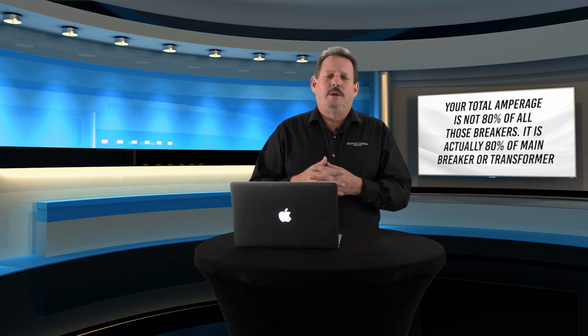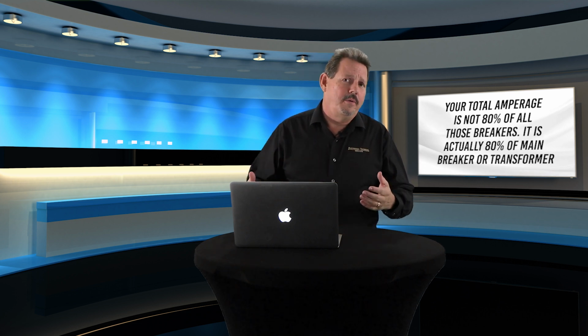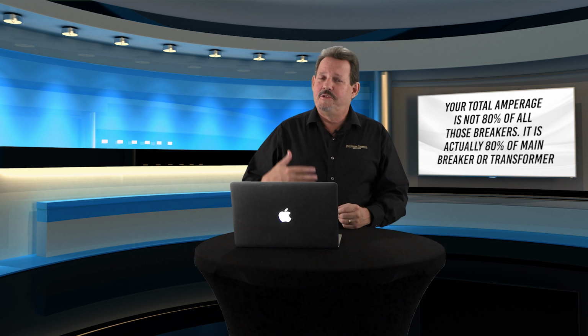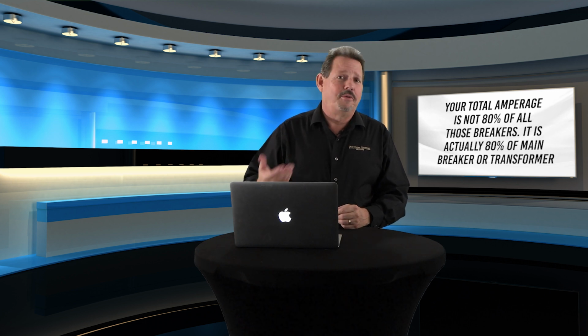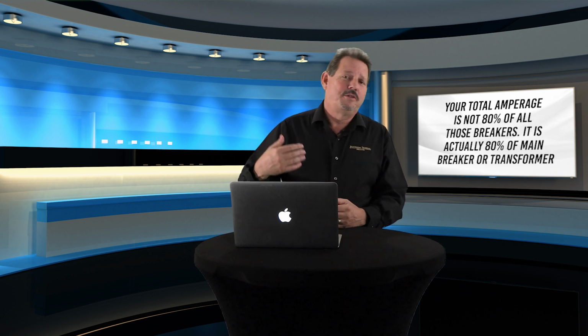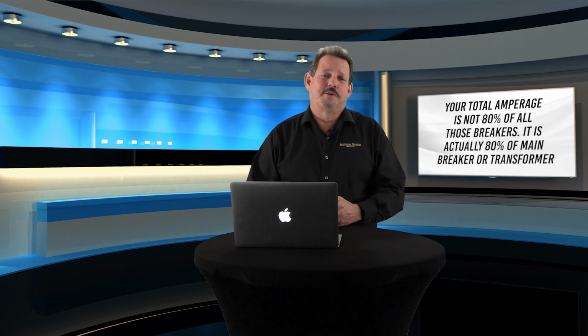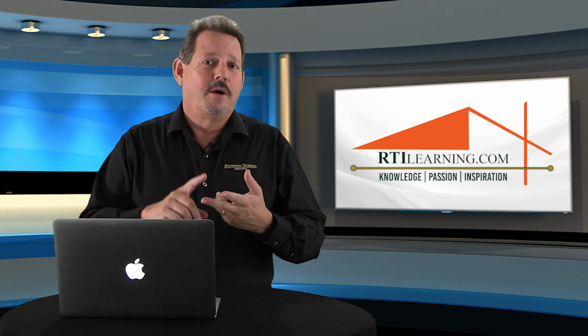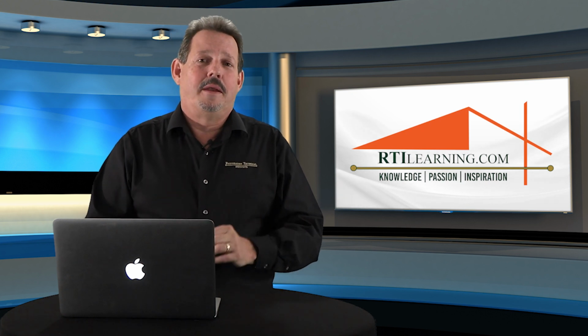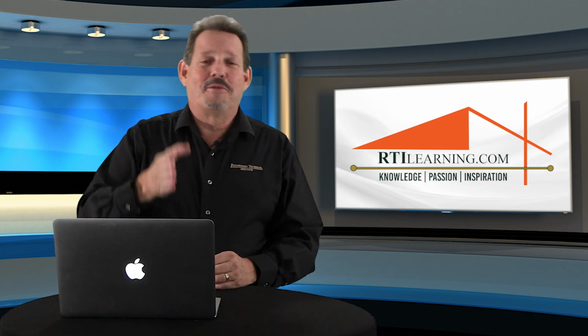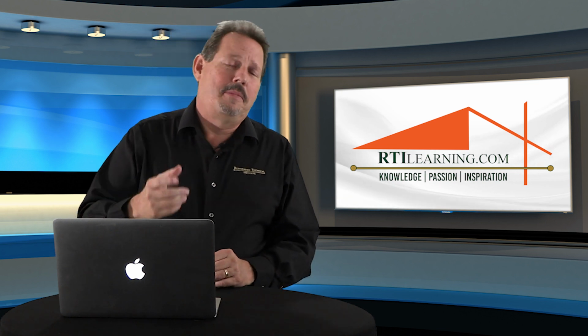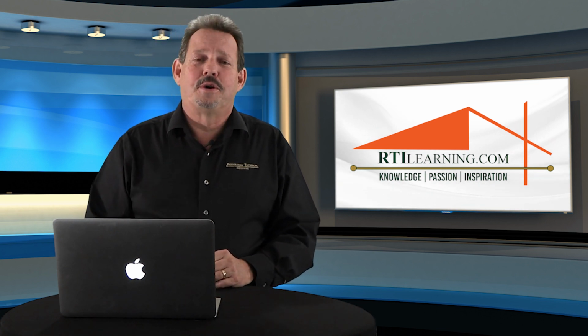So literally, you may have a couple hundred amps worth of circuit breakers, but you only have a 100 amp main; a 150 amp main is more common, and a 200 amp main is one of the largest you're going to see in residential. Of course, you have to take 20% off of that, and that's the power you have for the entire house to operate. That means stoves, dryers, all of your drying equipment, and everything else. And by dryers, I mean clothes dryers for the homeowner. These are big amperage items, along with an electric stove and ovens.